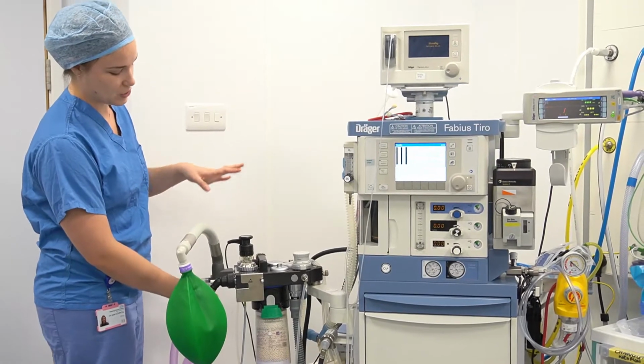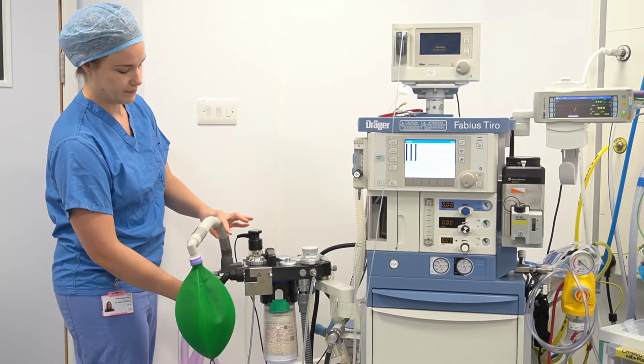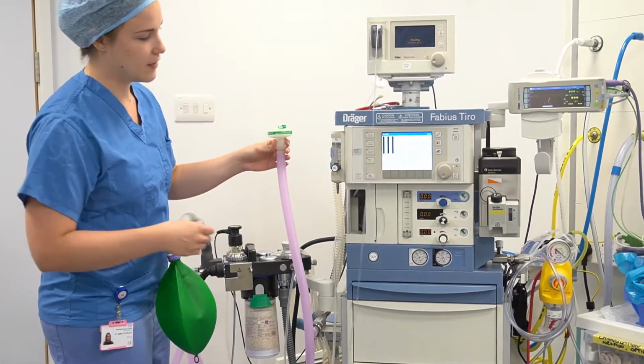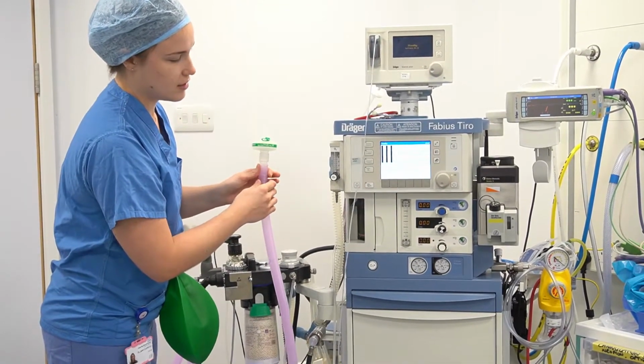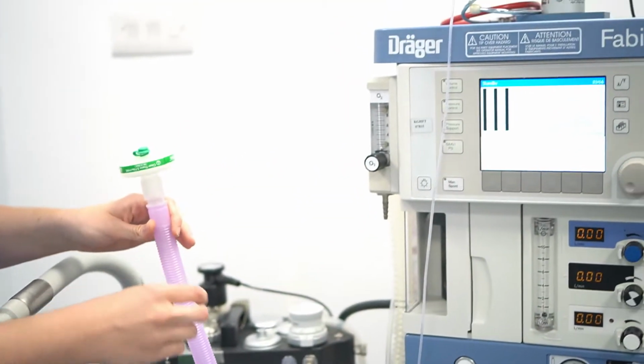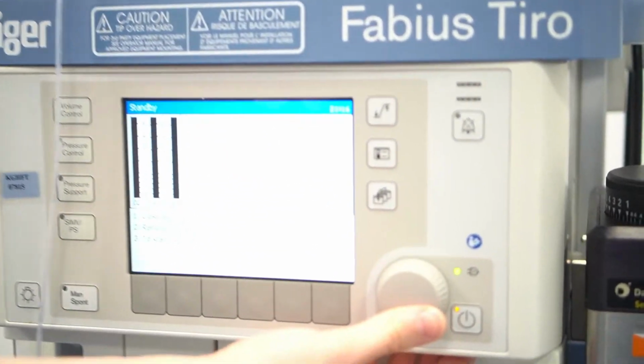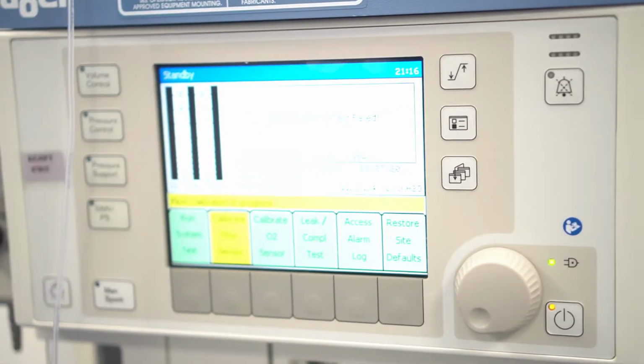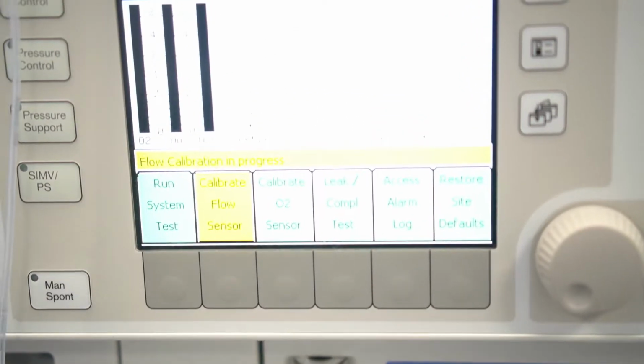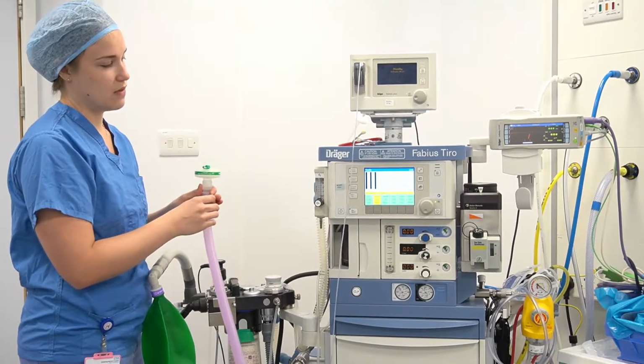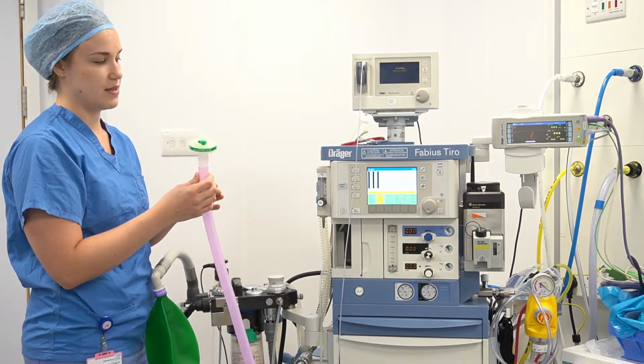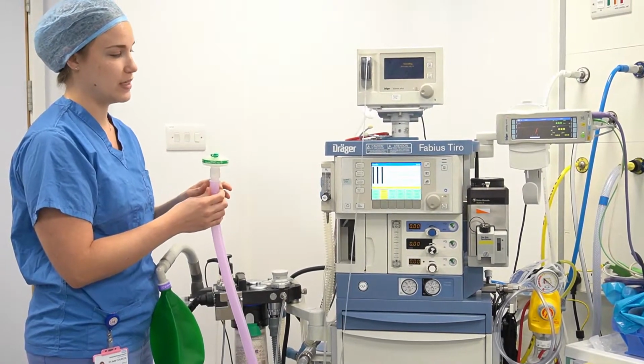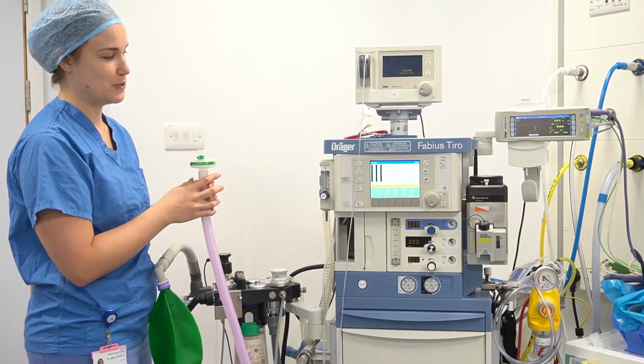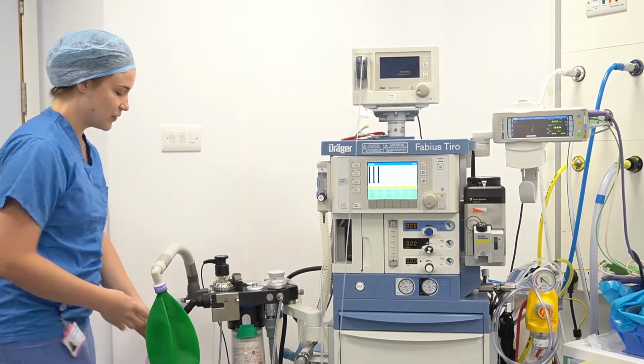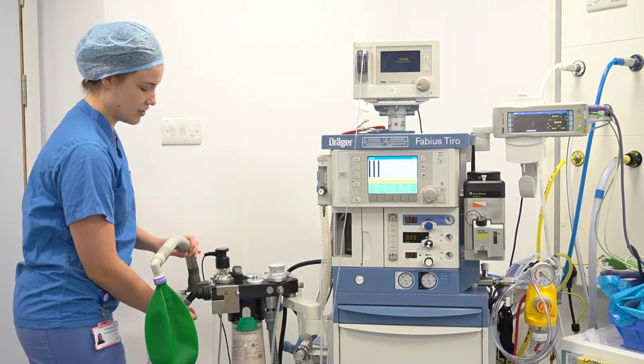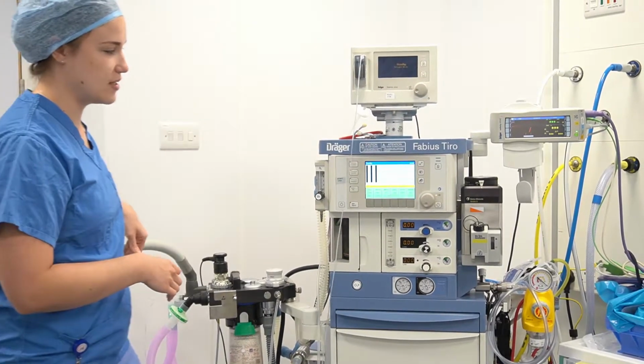So it's told us to remove your expiratory limb, which we're going to do. So we've done that. And then to start the flow sensor calibration, you push the rotary knob. So just pushing that, and then it's going to start the calibration itself. This normally doesn't take too long, and then it's going to tell you that the test has been passed, and then to just reconnect your expiratory limb, which we'll wait for it to do as it has here.